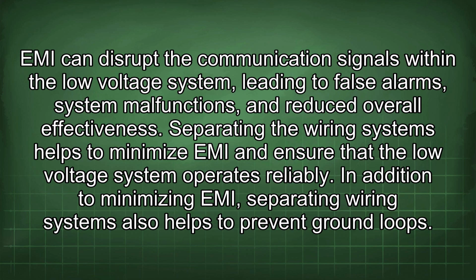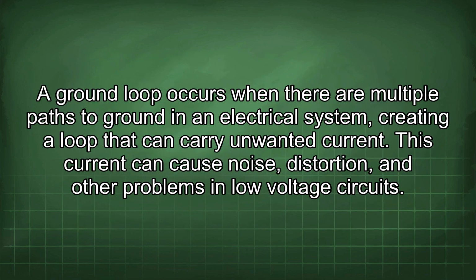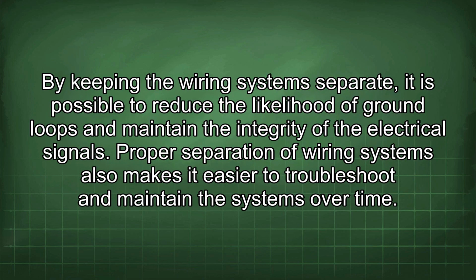In addition to minimizing EMI, separating wiring systems also helps to prevent ground loops. A ground loop occurs when there are multiple paths to ground in an electrical system, creating a loop that can carry unwanted current. This current can cause noise, distortion, and other problems in low voltage circuits. By keeping the wiring systems separate, it is possible to reduce the likelihood of ground loops and maintain the integrity of the electrical signals.